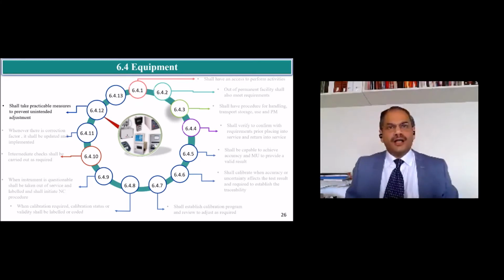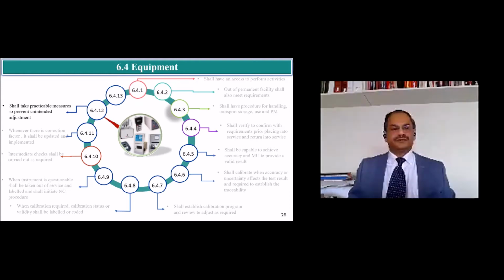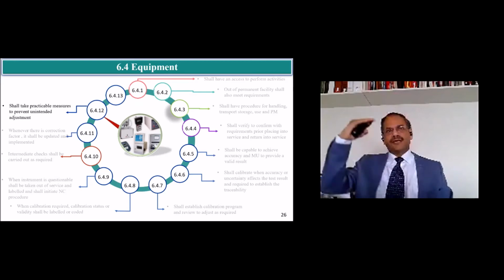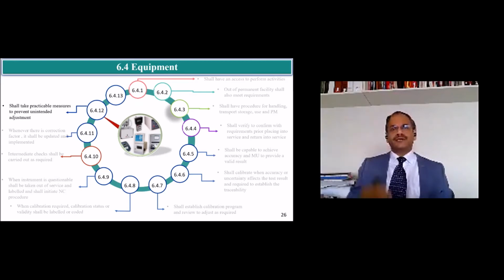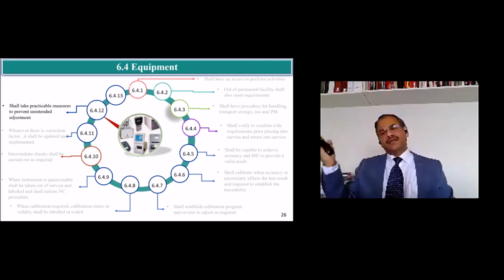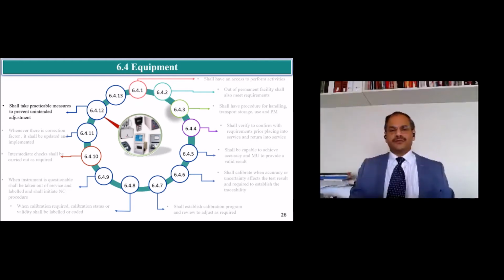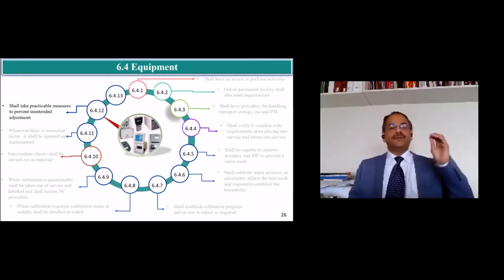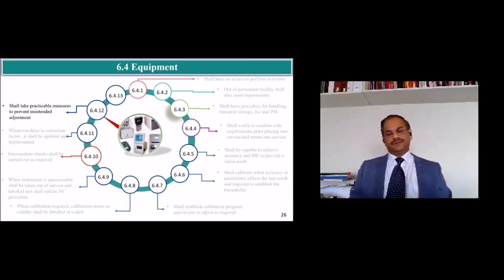So when you are calibrating equipment, what is the best way to prevent unintended use? Old equipment does not have anything, but now all the modern equipment has different layers of security. A technician can only go to perform the test, while a chemist or scientist can go to calibrate the instrument, and the maintenance person can access only the maintenance features. In some cases, it is not possible. That's why they are saying practicable measures to prevent unintended adjustment.